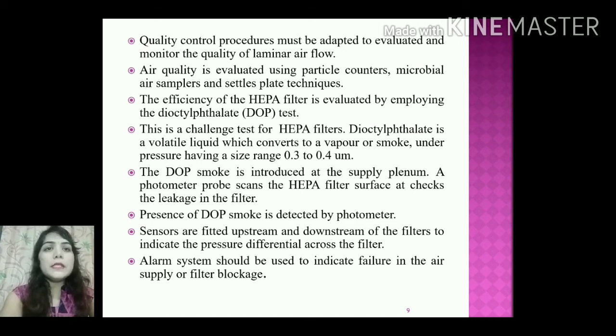The efficiency of the HEPA filter is evaluated by employing the dioctyl phthalate test, which is called the DOP test. This is a challenge test for the HEPA filter. Dioctyl phthalate is a volatile liquid which converts to a vapor or smoke under pressure, having a size range of 0.3 to 0.4 micrometer. The DOP smoke is introduced at a supply plenum.